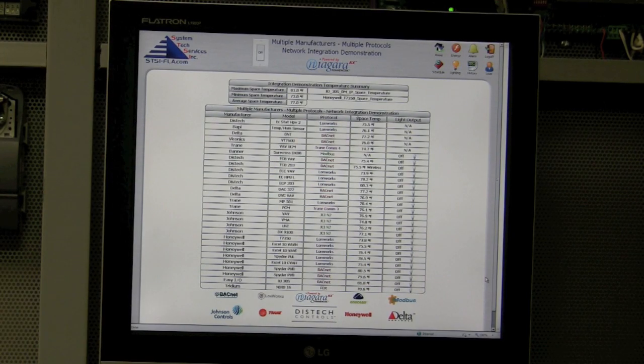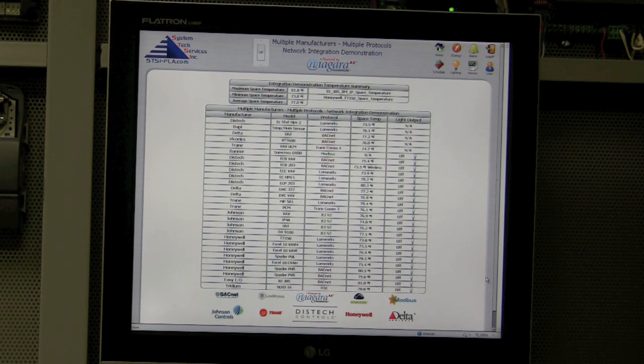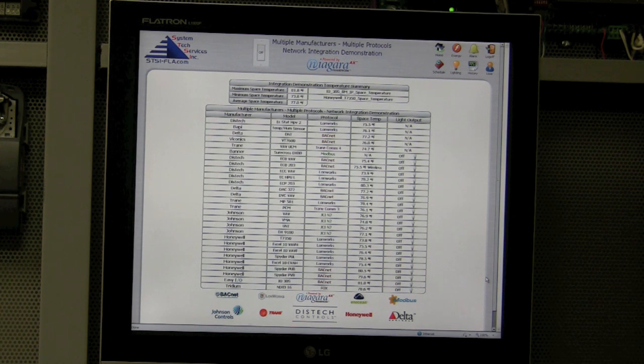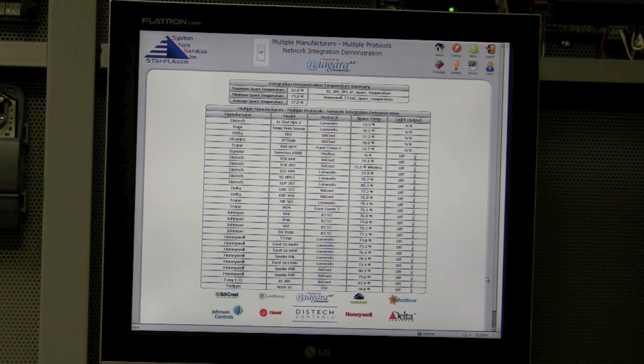We call it report card programming — we focus on the performance of individual pieces of equipment and controllers, and we tell you who the worst performers are so you can focus on that. Is it a mechanical problem? A control problem? A design problem? Our optimization is all demand-based — the VFDs, towers, and chillers are all ramped up based on zone demand. If a zone is undersized, you're wasting energy. We focus on those problem zones, make them right, and that pays for itself ten times over with the rest of the system.